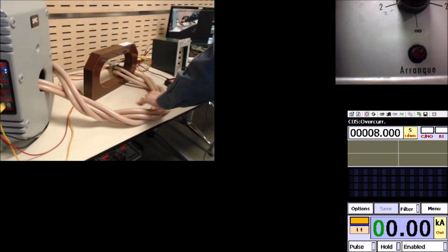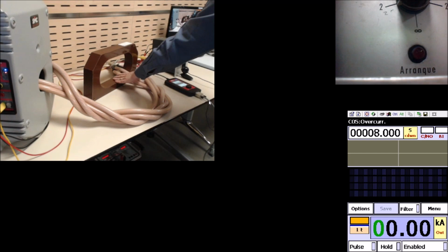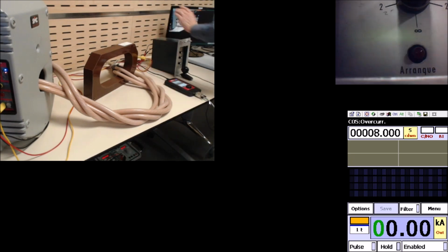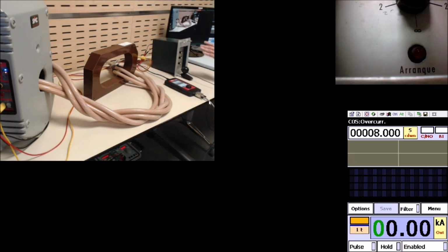So we are flowing high current across the primary winding of the current transformer, taking the secondary output to the relay. This small camera will show you here on the screen, in the top right corner, a small indicator when the relay picks up, I mean, when the relay is measuring fault current. So you can have some feedback of the relay response to the different values of current that we are going to inject. And at the bottom right of the screen is a replication of the Raptor commander.